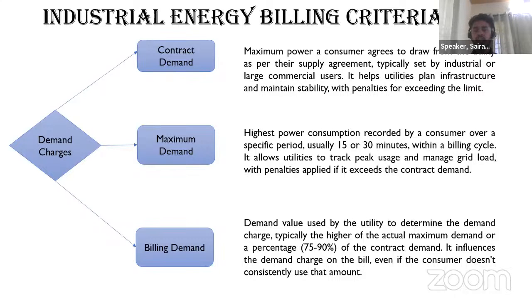And also the agreement says that if the contract demand goes beyond that kVA limit, then a penalty will be levied on the user end. Then coming to the maximum demand, it is usually checked for a period of 15 to 30 minutes in a billing cycle. Every 15 to 30 minutes, they check the maximum kVA that has been drawn at the end of the user. Then they conclude at the end of the month what the maximum demand was. In reality, the maximum demand has to be less than the contract demand, so that we can avoid the penalties. Then coming to the billing demand, the billing demand usually is under an either-or condition.